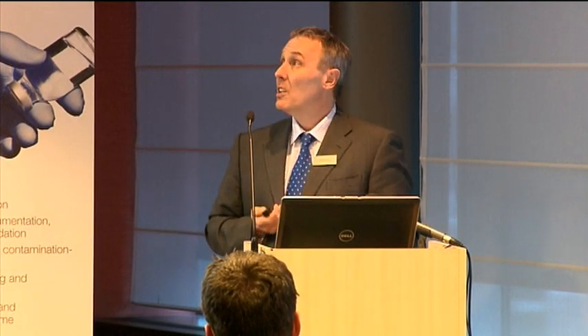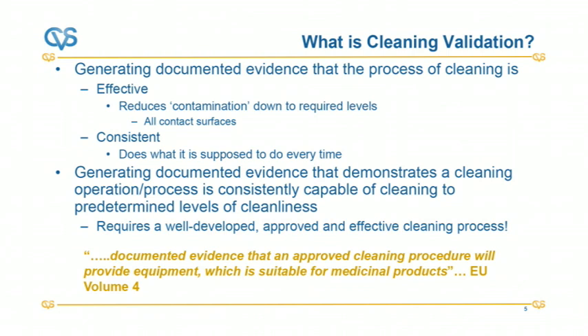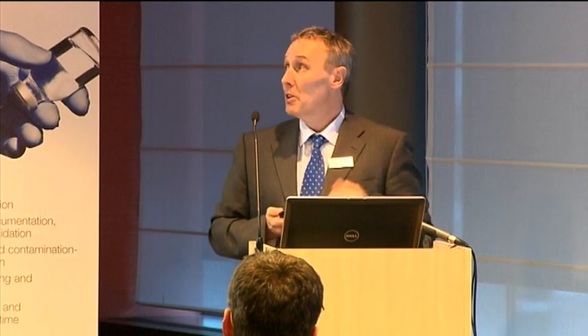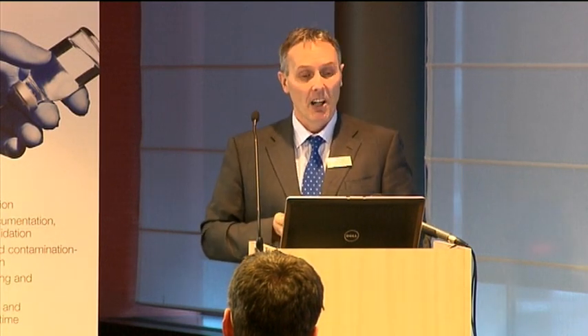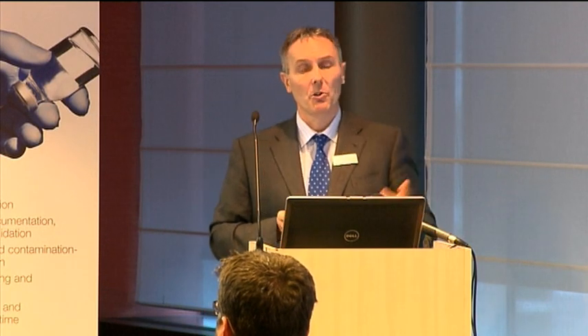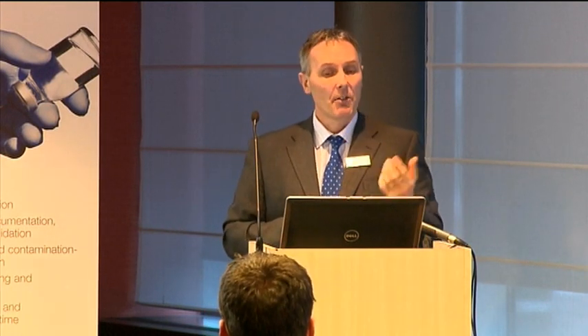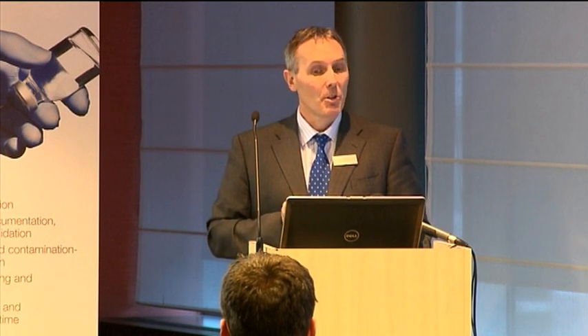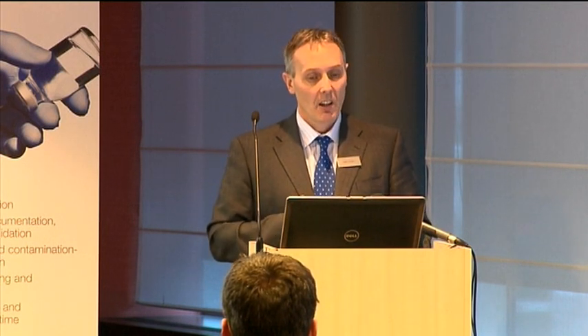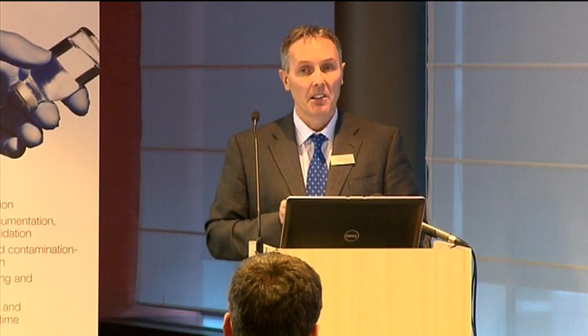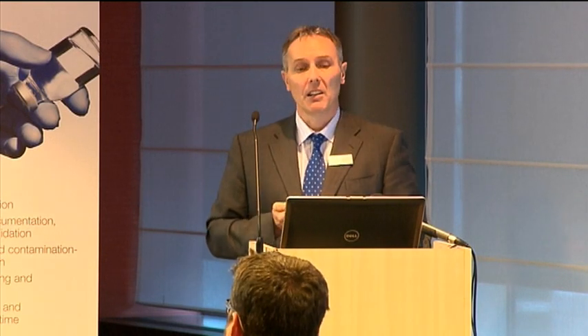So we reduce contamination down to required levels on all product contact surfaces, or all potential contact surfaces. We also make sure that we generate evidence that it's consistent, so we don't just do it once. Probably we do it three times or more to prove that it can be done every time. So we can summarize all that by saying: generating documented evidence that demonstrates a cleaning operation or process is consistently capable of cleaning to predetermined levels of cleanliness.